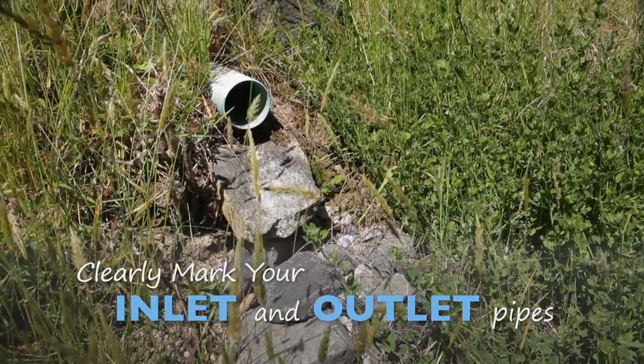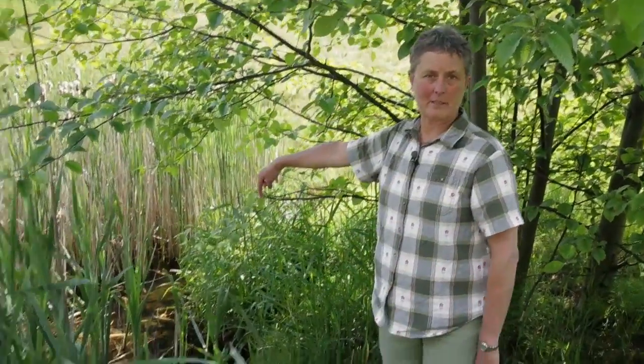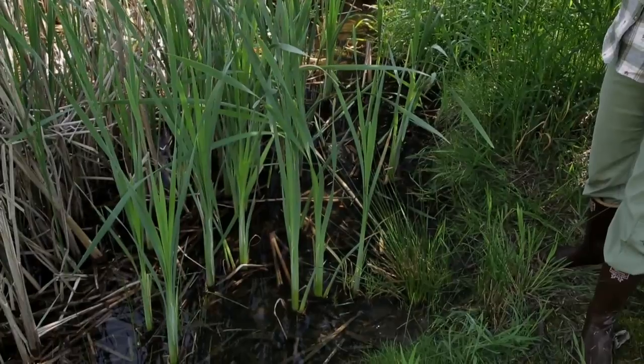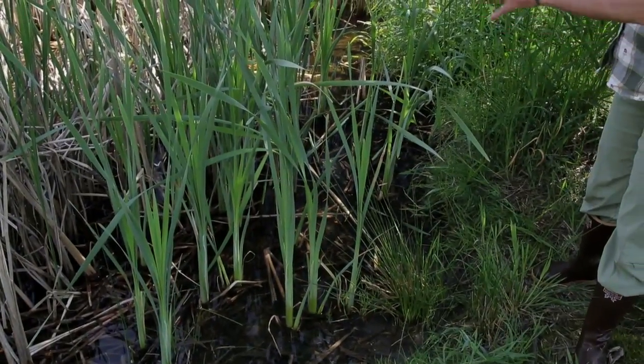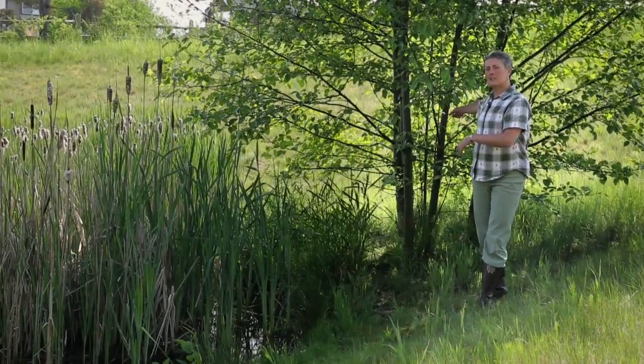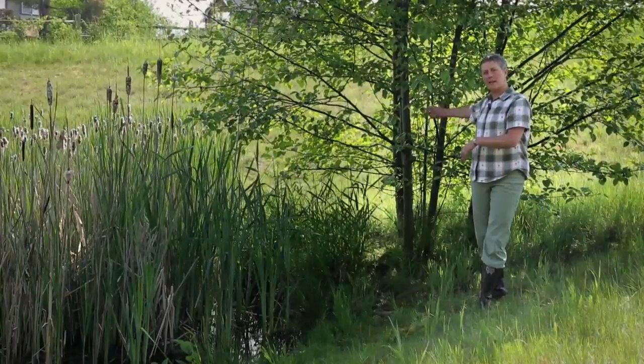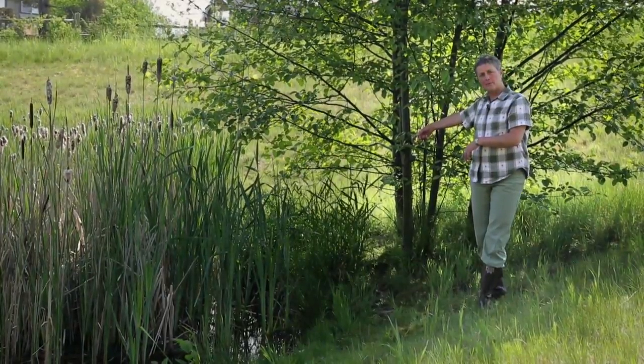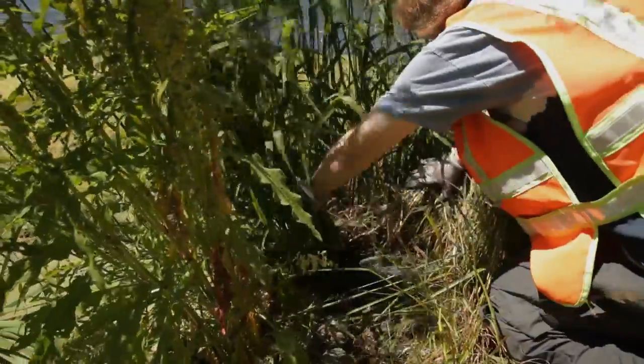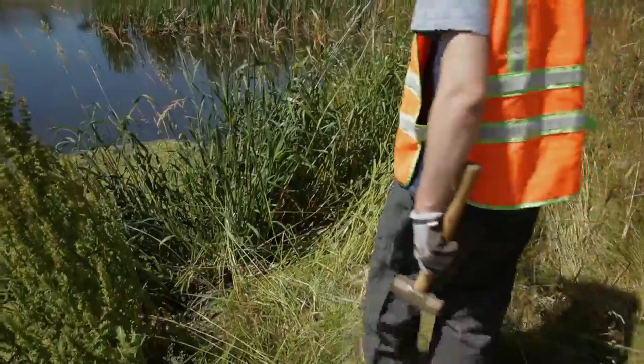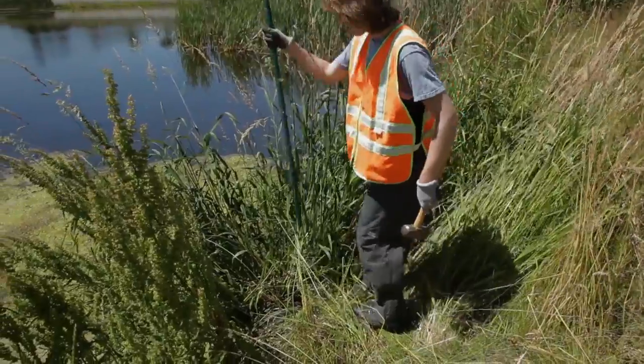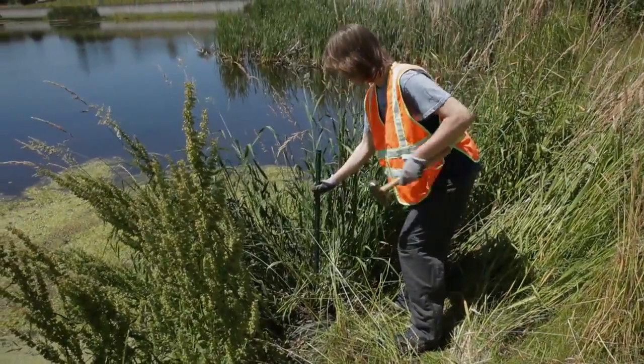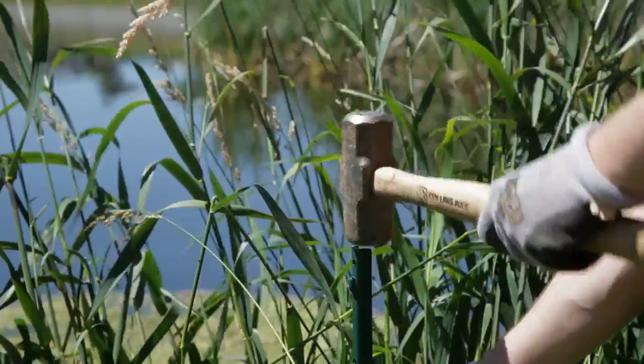This is a good example of vegetation management that is not happening. This is the inlet for this stormwater pond, and we can't even see it because it's covered with all this vegetation here, including this tree, and these tree roots could be damaging the inlet pipe. So we want to clear this vegetation out of here, keep it out of here. So we need to manage this vegetation so we can see the inlet, and we want to mark it with a pole or a fence post so we can find it.